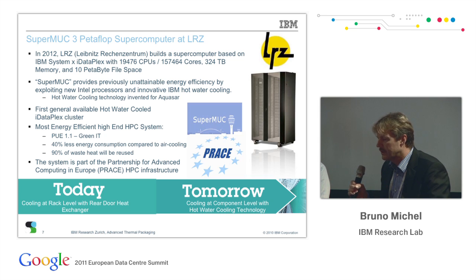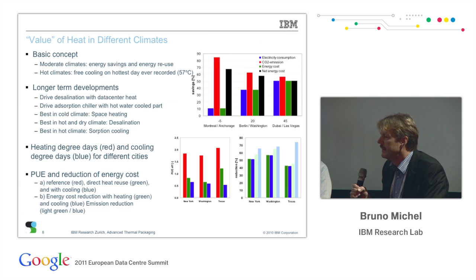We don't need any chillers, and we only need a water pump to be driven. And we have seen water pumps can be driven between 1% and 5% of energy. Yeah. We invest a little bit more of pumping power, as our heart does, because we can increase the heat transfer coefficient between the chip and the water by having a little bit more pressure drop and microfluidic capillaries. Next slide. So we look, of course, at the value of heat in different climates.